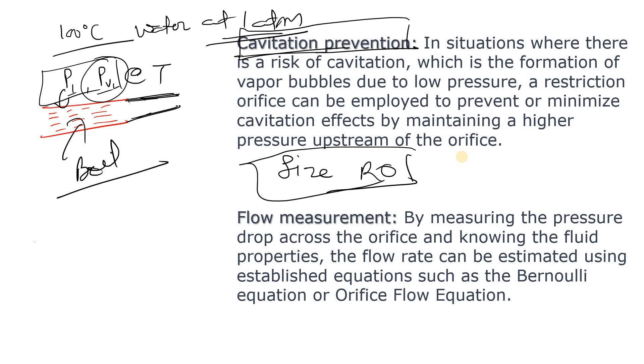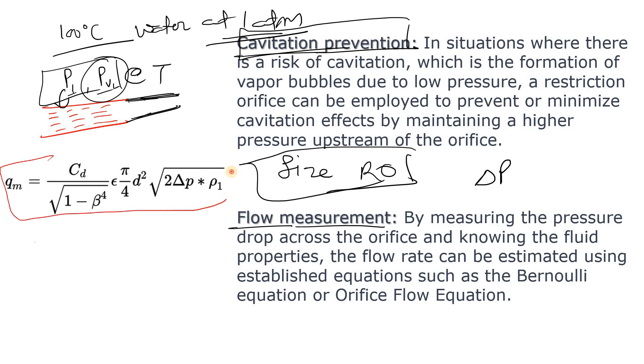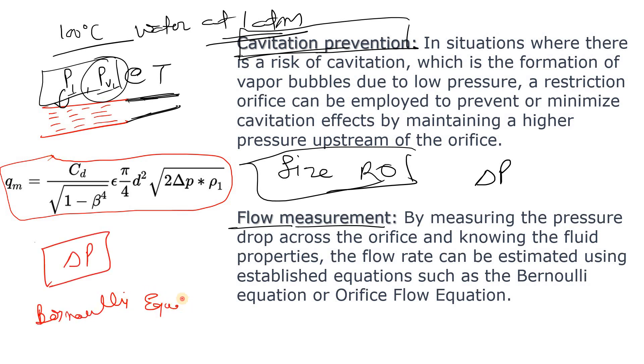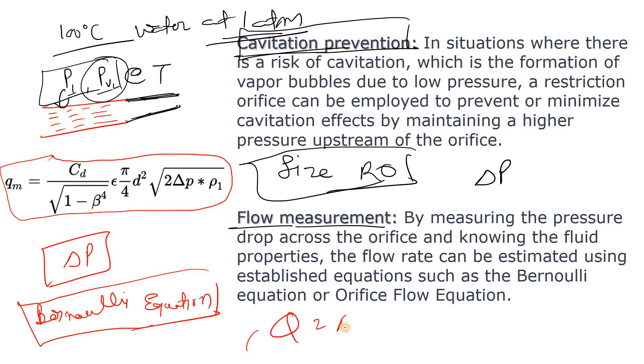Also, as you are creating a delta P across the RO, you can use it to find out the flow rate. The formula — which we studied in undergraduate classes — is derived from Bernoulli's equation, the same as used in a venturi meter or orifice plate. With Bernoulli's equation and the continuity equation Q = A×V, you can derive the equation for flow measurement when delta P is known.